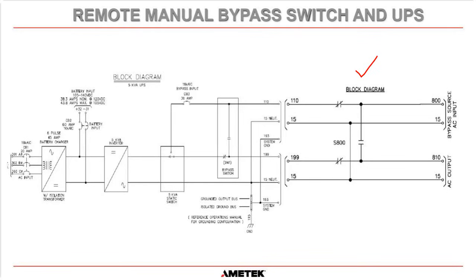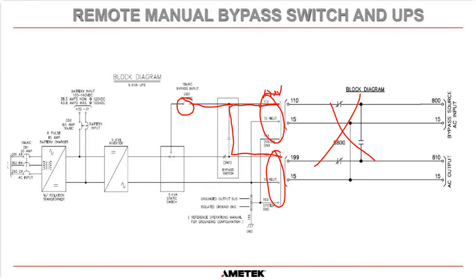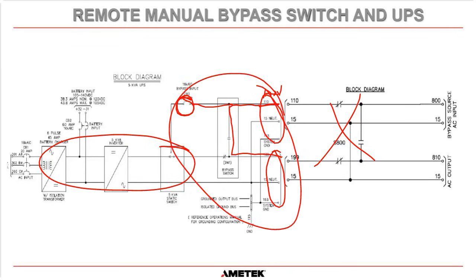So you can see here that this original UPS has what we call a manual bypass switch on the UPS itself. Let's say we've got 120 volts coming from the bypass. Let's forget about this just now. If we had 120 volts coming in here and moved this to bypass position, it would flow through there. Now remember, these terminals are inside the UPS. This breaker, the power will go to here. This breaker is inside the UPS. So yes, we can go and work on this UPS, but we can't do it completely volt free, because inside this UPS we are going to have live terminals. I hope you understand that.